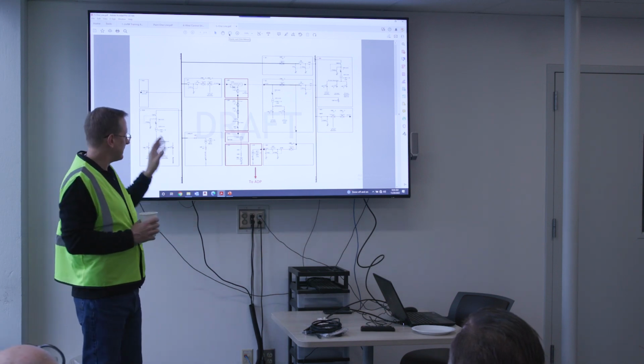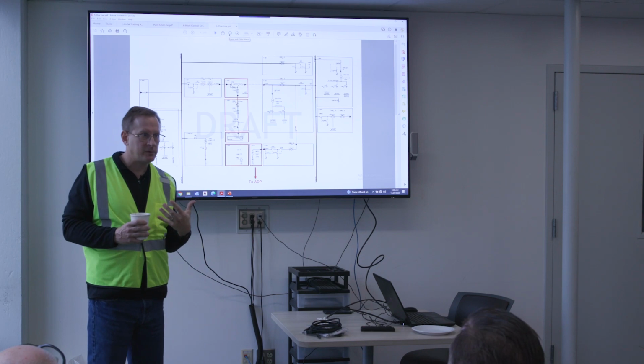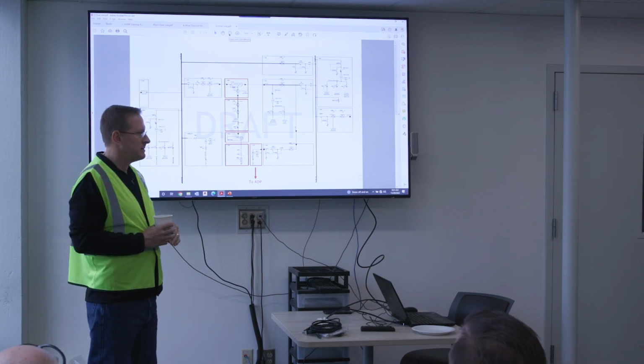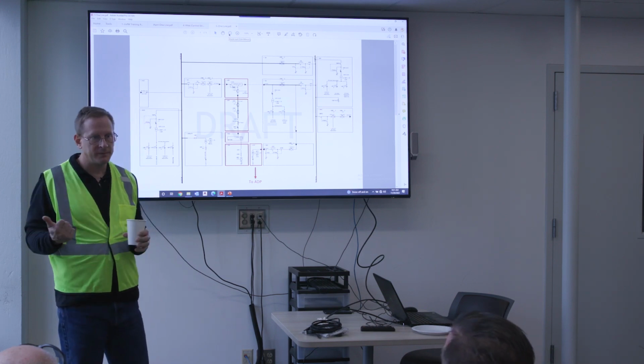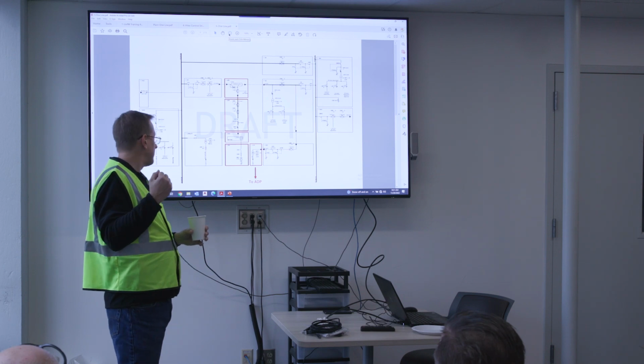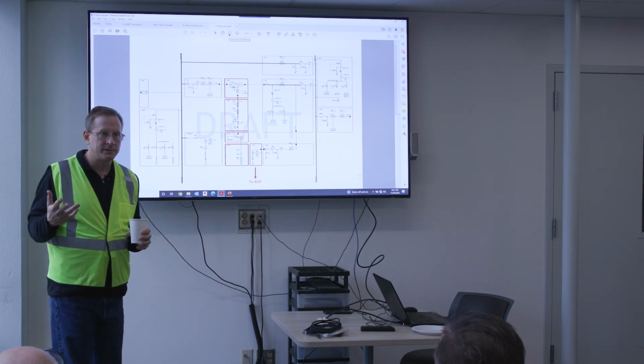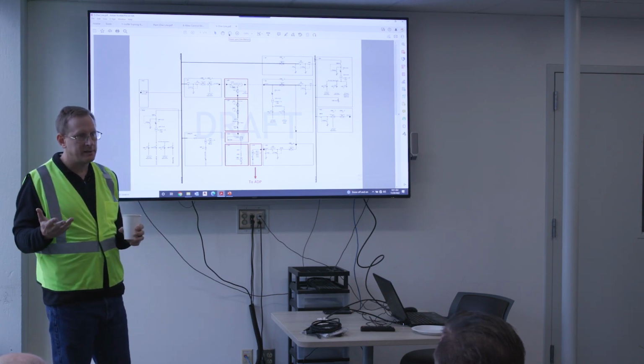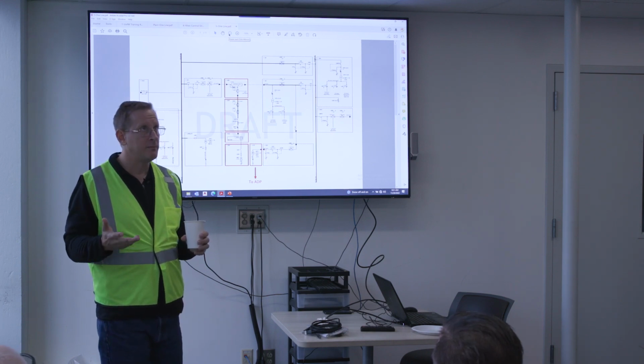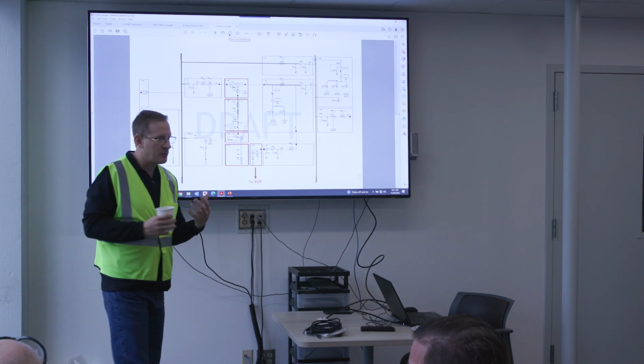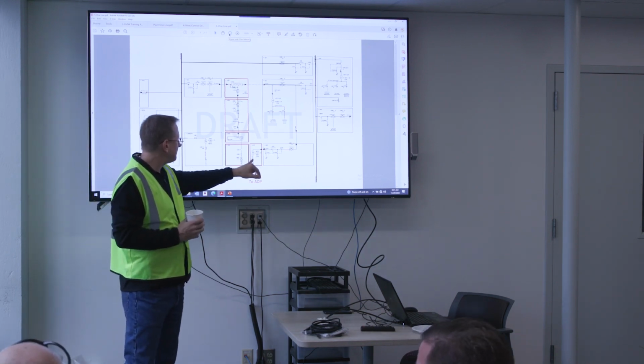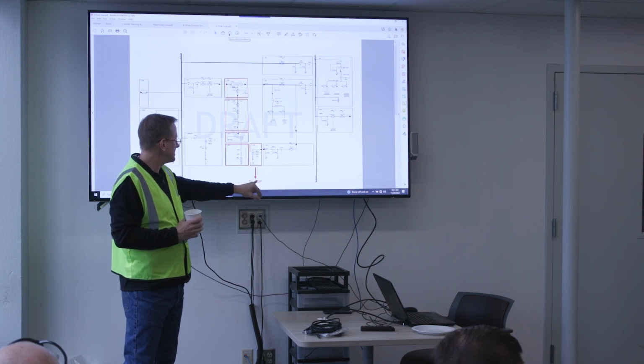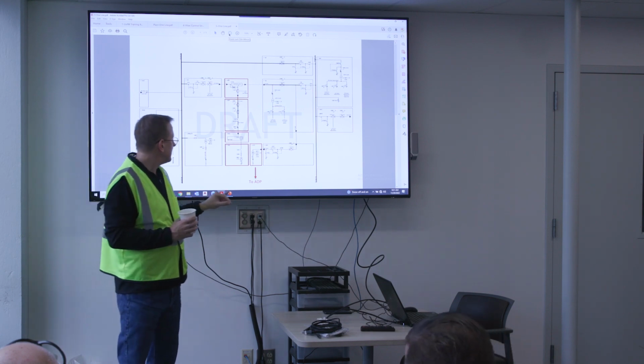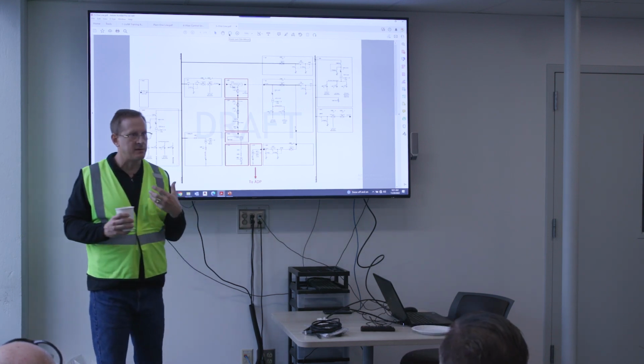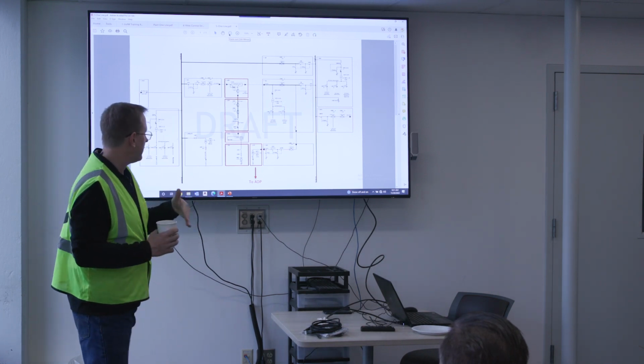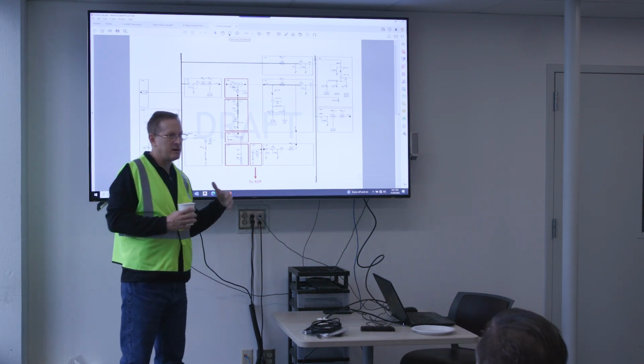Now, this is all, again, 4160 medium voltage. We have a lot of 480 volt loads that we need to supply for our system for our auxiliaries. For example, the radiator works off of 480 volts, three-phase. Our RSP is a 480 volt panel. Our UCP basically requires 480 volts as well to operate. So we have a lot of low voltage 480 volt loads, and that's why we need a GDP, so that we can get some voltage to our low voltage auxiliaries, and they're fed by our ADP, which stands for Auxiliary Distribution Panel. So that's our low voltage 480 volt three-phase panel that is going to feed our auxiliaries.